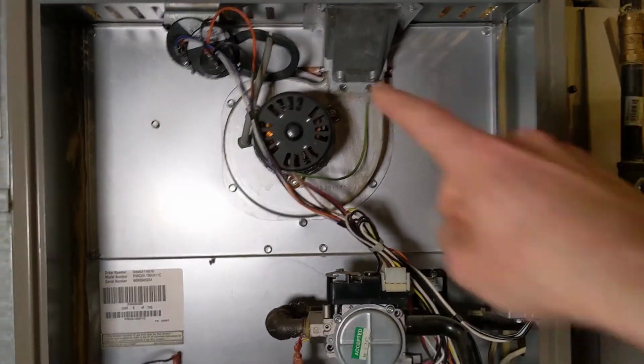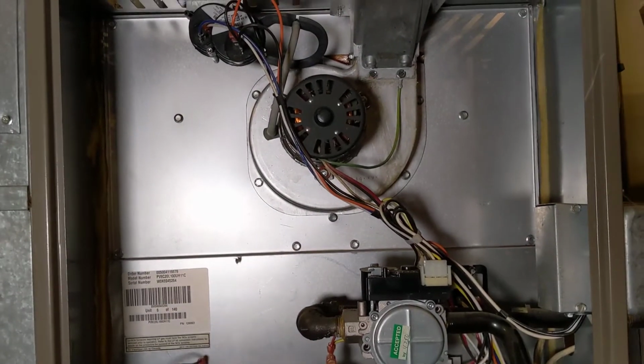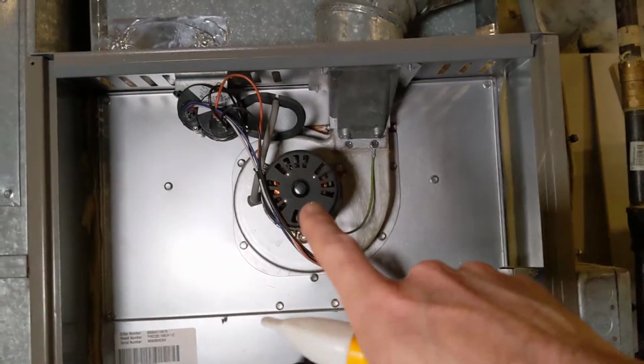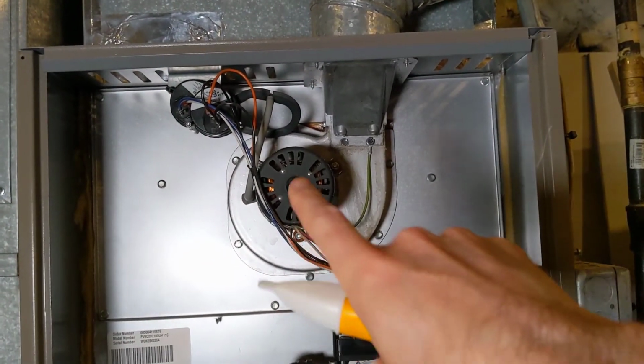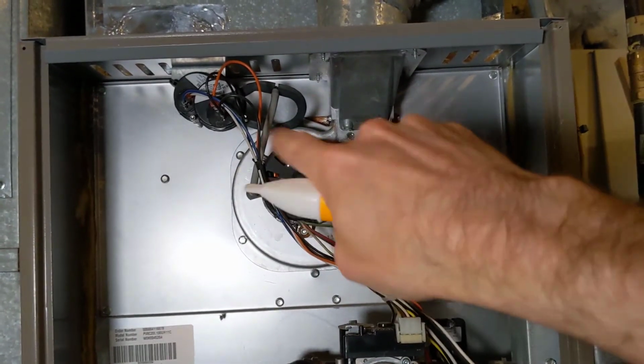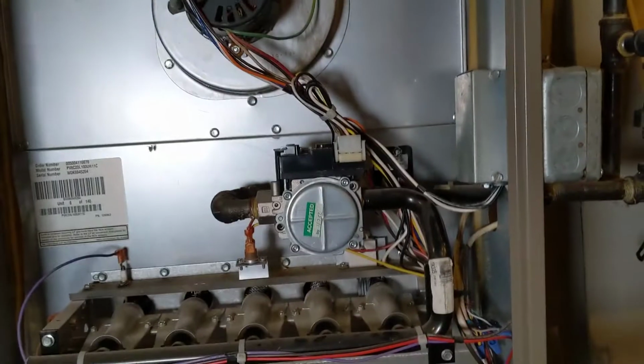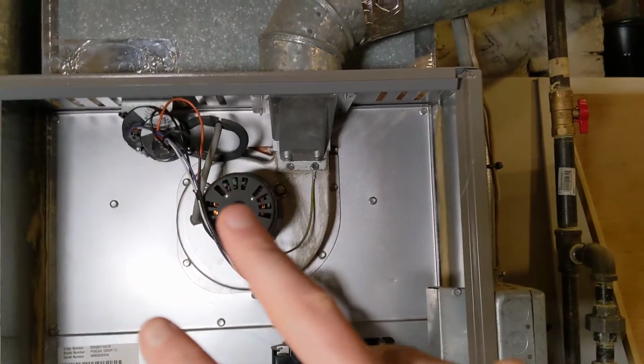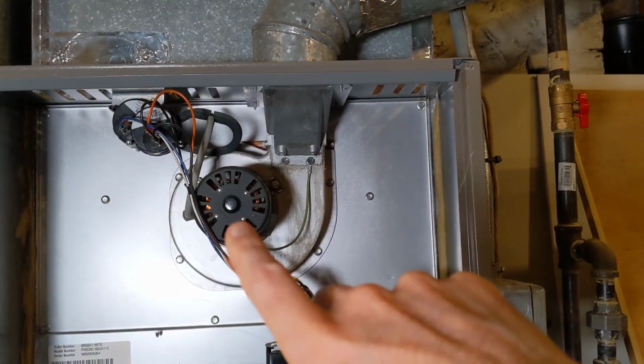Again, let's go back to the beginning. What's the first thing that fires off? Well, it's the inducer draft motor. What we need to do is investigate that first piece. If that doesn't come on, then we know the problem starts there. We have to have draft before anything else fires up. The two common problems if that does not fire at all is either that motor's bad or the board is bad.